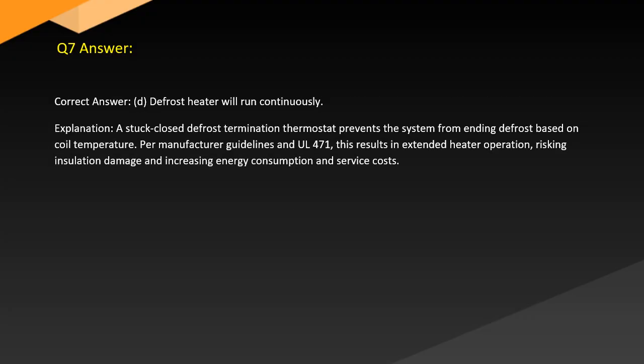Answer. Correct answer: D. Defrost heater will run continuously. Explanation: a stuck-closed defrost termination thermostat prevents the system from ending defrost based on coil temperature per manufacturer guidelines and UL 471. This results in extended heater operation, risking insulation damage and increasing energy consumption and service costs.